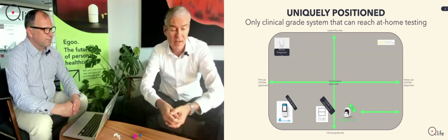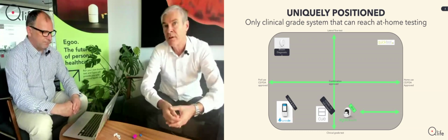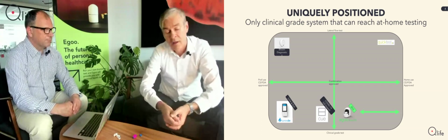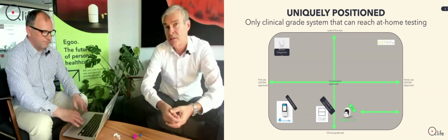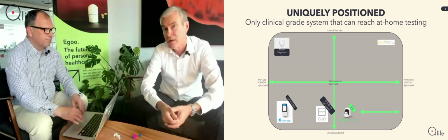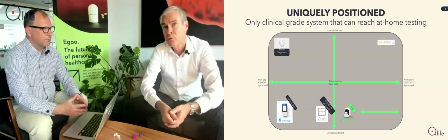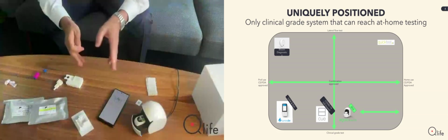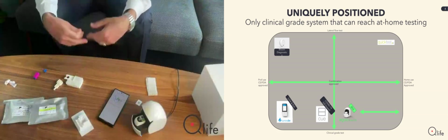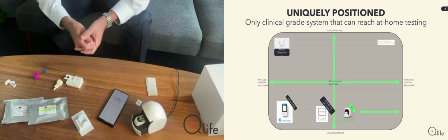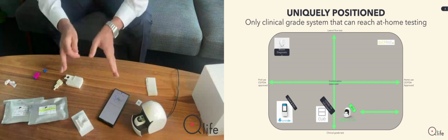And I can generally say that before it was under the IVDD directive, which was actually it's a big change, because in the old days you could self-certify. That means that we could put this product CE marked by ourselves on the market, and then we would be audited once in a while, once a year. But the product was CE marked.